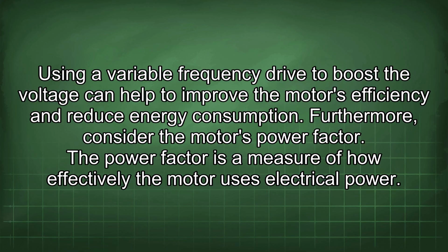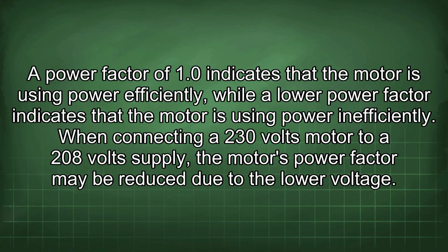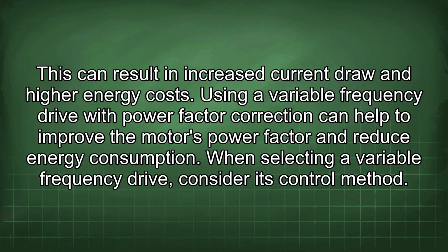Furthermore, consider the motor's power factor. The power factor is a measure of how effectively the motor uses electrical power. A power factor of 1.0 indicates that the motor is using power efficiently, while a low power factor indicates that the motor is using power inefficiently. When connecting a 230 volts motor to a 208 volt supply, the motor's power factor may be reduced due to the lower voltage. This can result in increased current draw and higher energy costs.